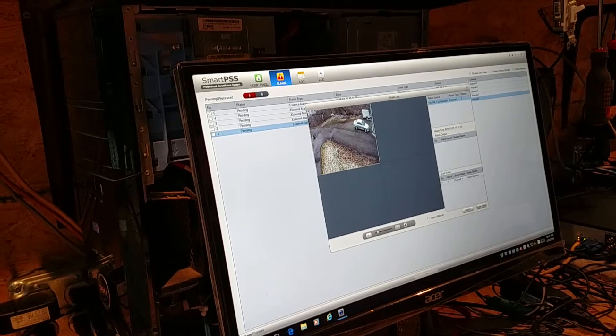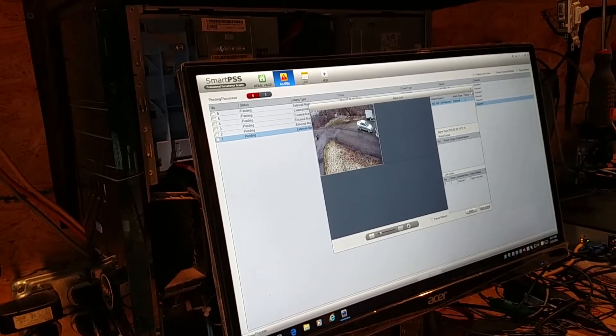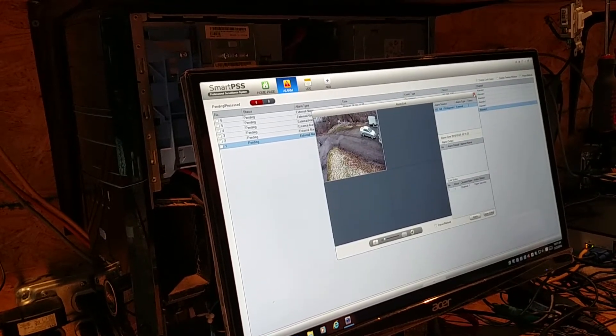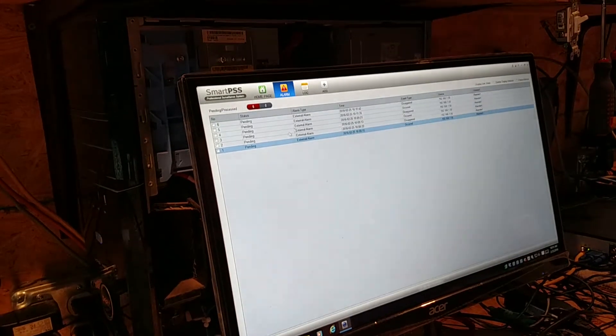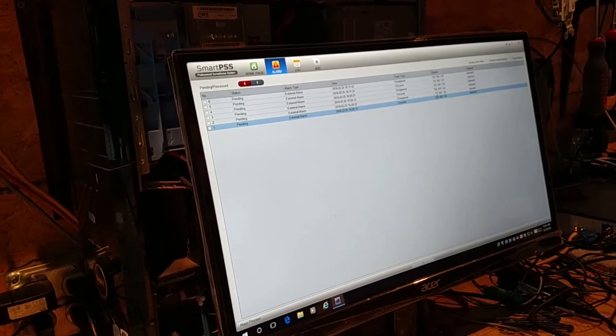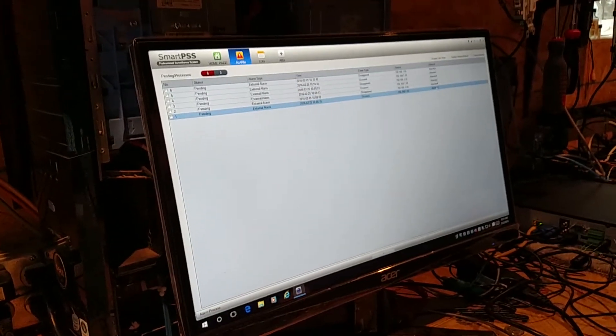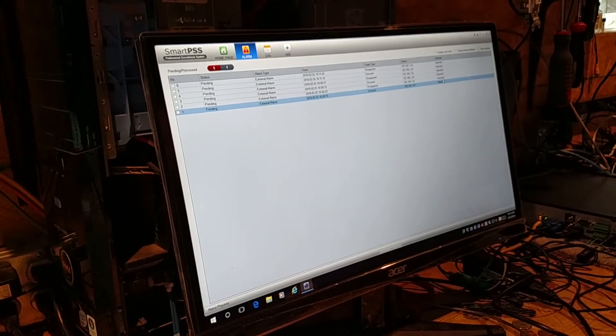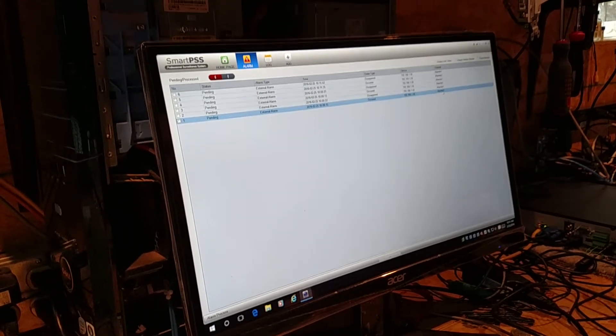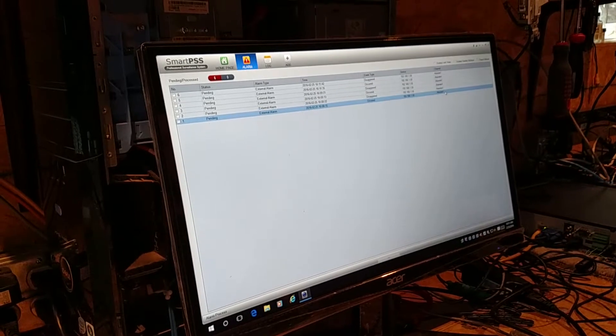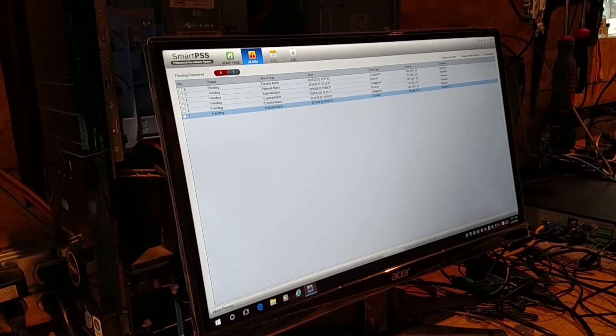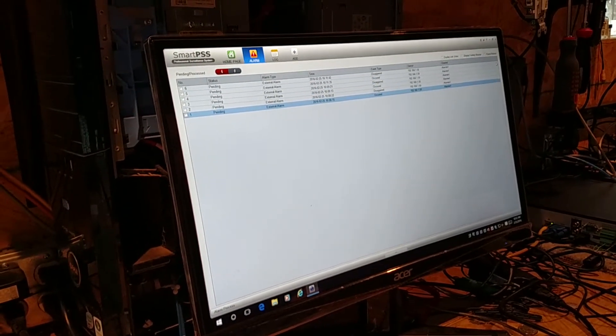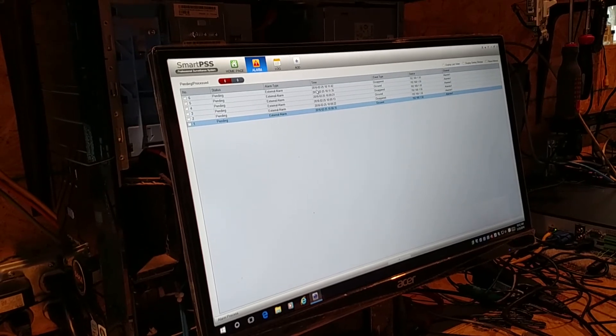So, if the operator just has this alarm page opened up on one window or one monitor of the computer, he can see when the alarms came in. He doesn't know what the alarm is, he knows it's alarm in one. This channel needs to be a description, which you can create when you create the alarm, and right here needs to be a link to play the recorded video associated with this alarm.